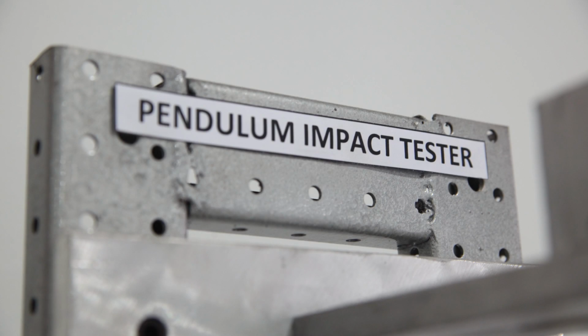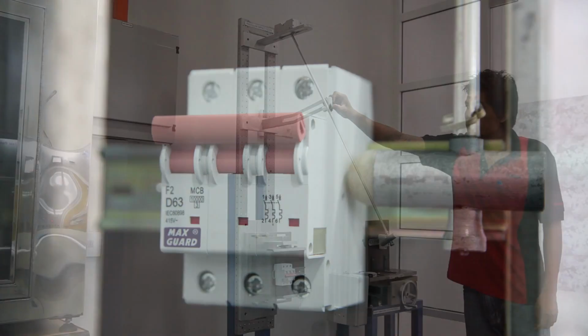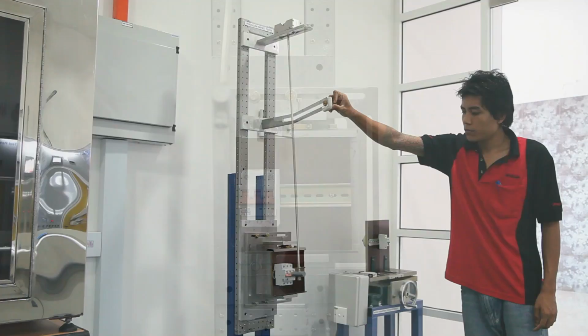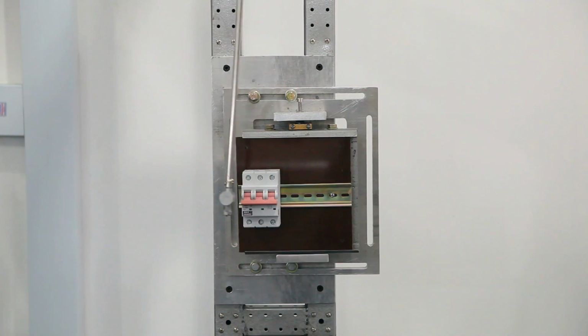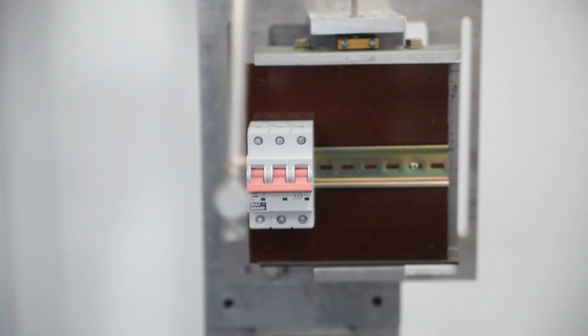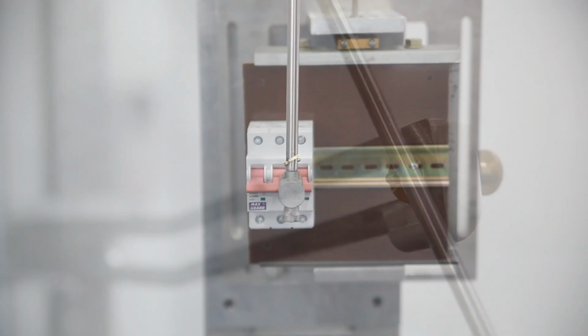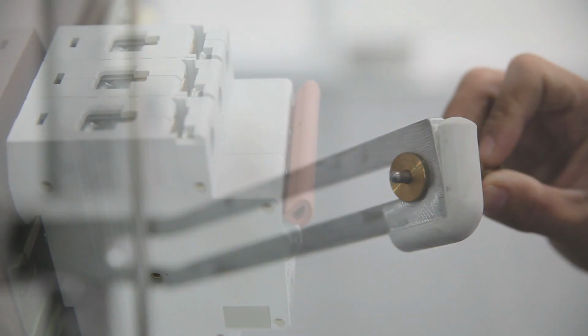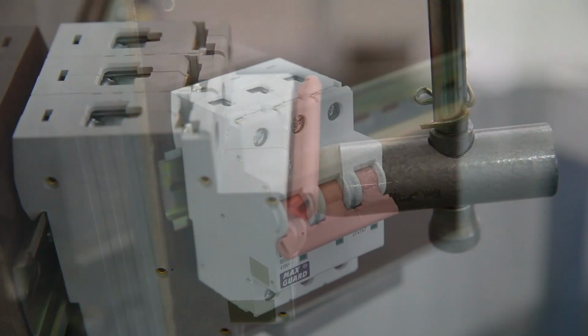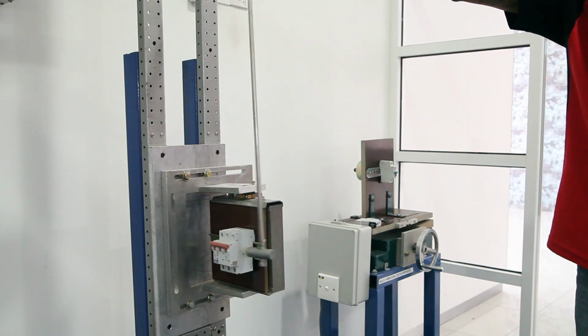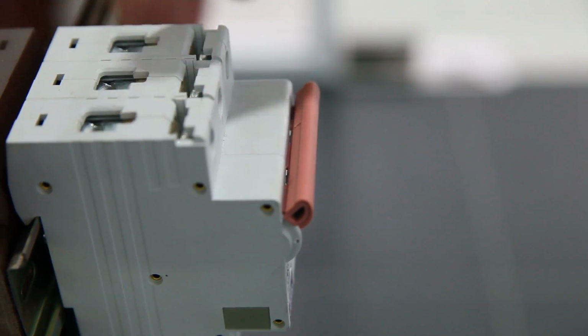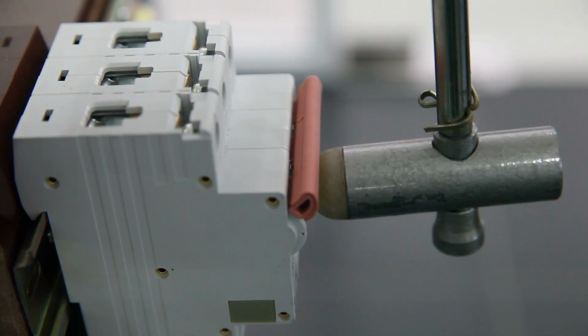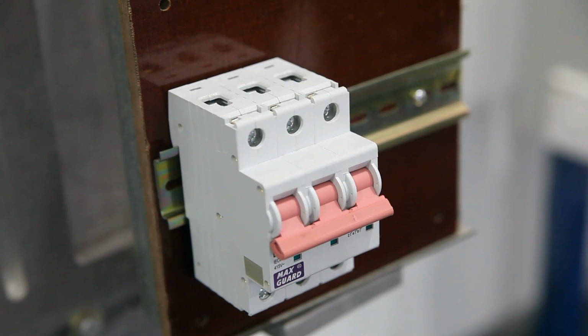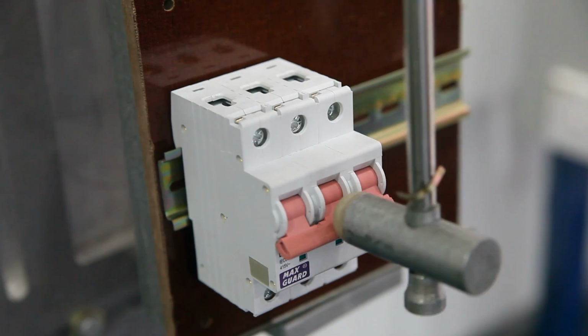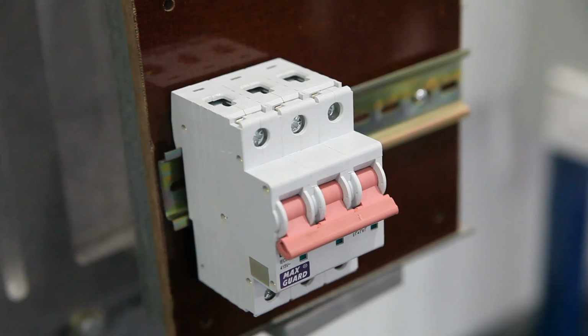Pendulum Impact Tester. The Pendulum Impact Tester is a standard designed equipment to perform the mechanical impact tests on MCBs and RCCBs to ensure that products are able to withstand inadvertent knocks and breakages that expose live parts, rendering them hazardous. The MCB and RCCB under test is mounted in the normal vertical operational condition and is subjected to 10 impacts using the nylon pendulum hammer, which is released at an elevated height of 100 mm from the lowest position.